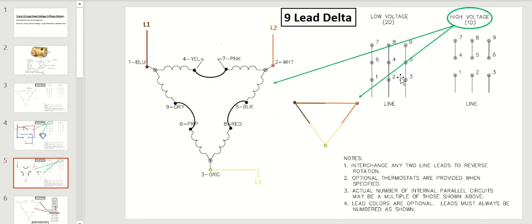When you switch to the high voltage connection, now we're going to put a jumper between 4 and 7, 5 and 8, 6 and 9, like it says here, and we're going to connect the higher voltage to L1, wire 1, wire 2, wire 3. And now, since we have the higher voltage across a series circuit of 2 inductor windings, we're going to actually split the voltage. So you see the voltage across the winding did not really change from a low to a high voltage connection. It's just now they're in series instead of a separate power on each winding.